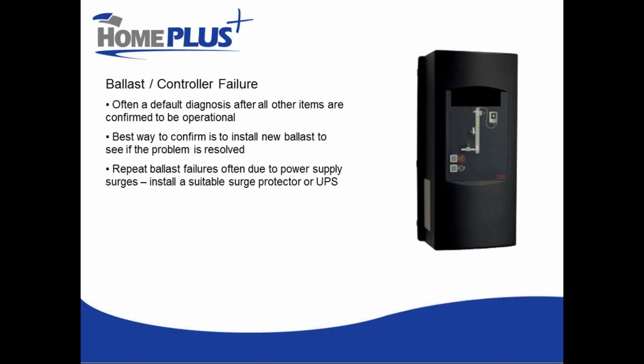Ballast failure is quite rare, but can happen. It's kind of the last thing we go to. Sometimes, like in the ballast pictured here, there'll be lights or indicators on the unit that can help you determine which component may be the problematic item in the system. So sometimes it will indicate a ballast failure or problem. And generally, those indicators are correct.